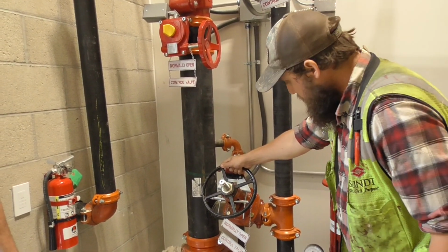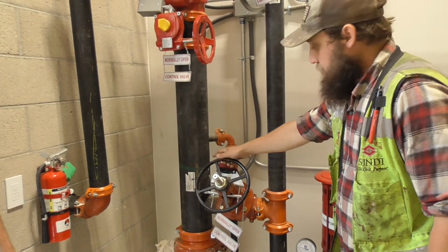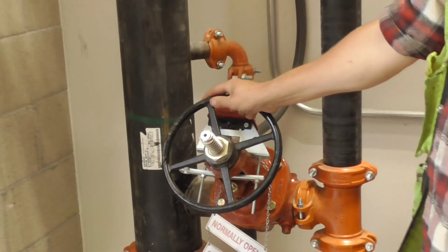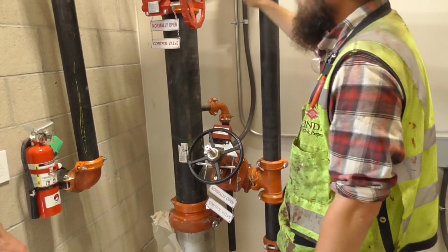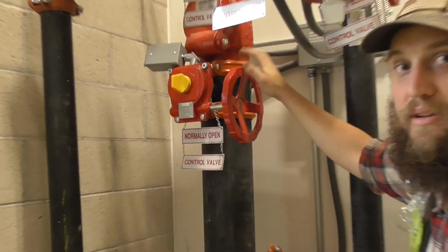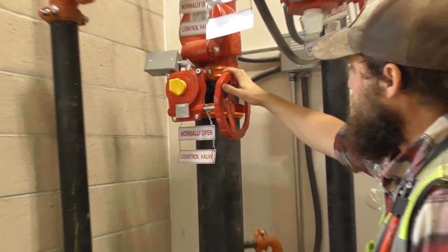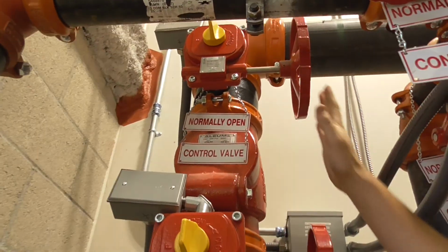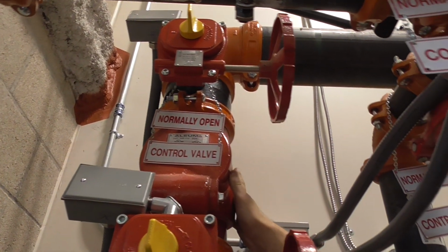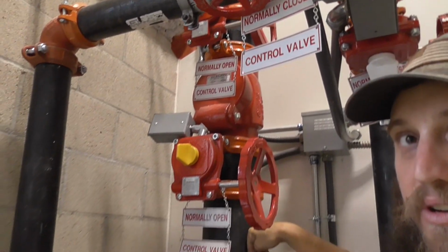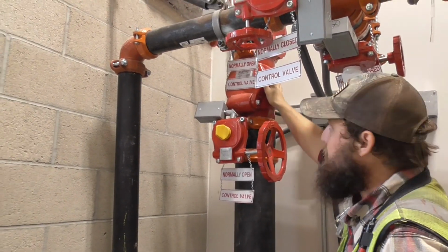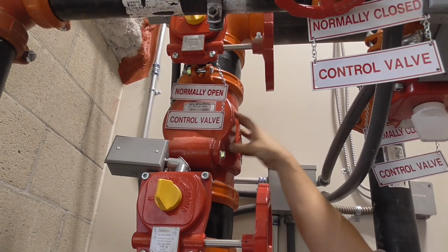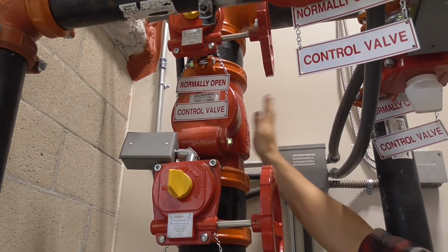This control valve here directly feeds the pump. So if you ever need to service the pump, you will close down this control valve. If you ever need to service the bypass or any other systems, you will close down this control valve. Okay? We have another control valve here. In combination with these two, we have a check valve here, which does not allow water to backfeed into your underground. If you ever need to service this, you will close both control valves. That will shut down water, and you'll be able to safely remove this, clean it, service it, replace it, whatever you need to do.